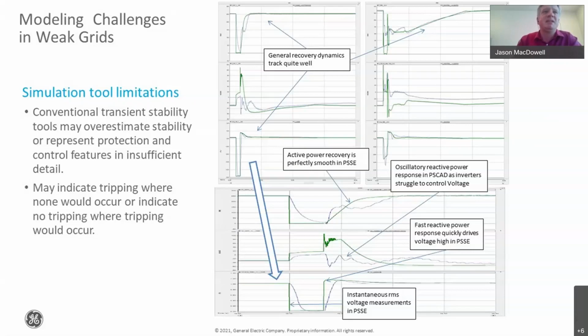In some cases, the stability models don't represent all of the capability of protection and control in sufficient detail, and may either not represent all of the conditions that will actually happen and be over optimistic, not showing the problems that may occur with control interaction because they simply don't have the fidelity, or they may indicate tripping in the model where it's actually just fine. It depends on the assumptions in the model that you use.